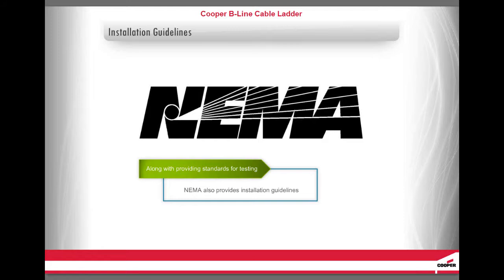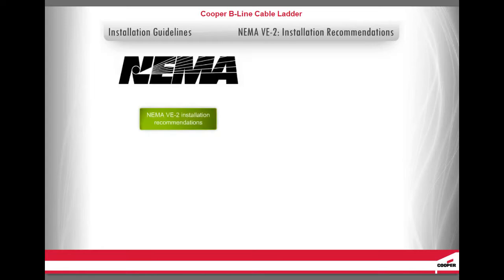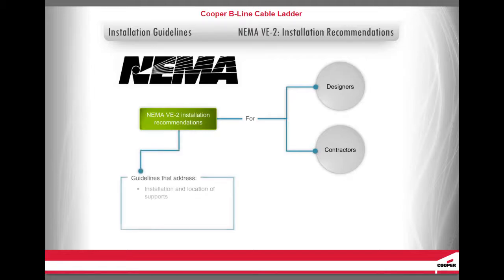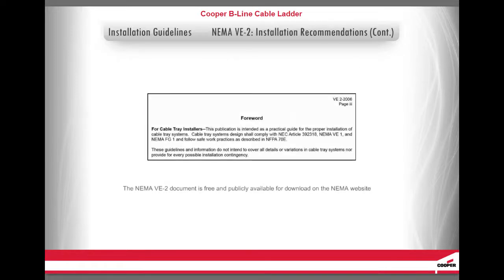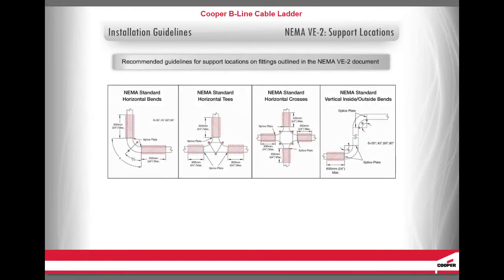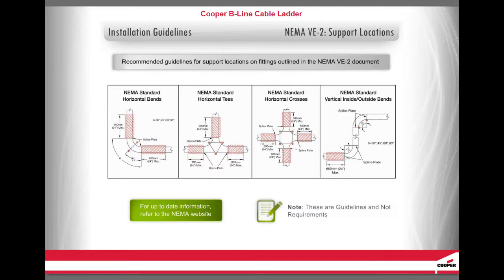Along with providing standards for testing, NEMA also provides installation guidelines. The NEMA VE2 installation recommendations are for designers and contractors. They are guidelines that address installation and location of supports, field modifications, grounding and bonding, as well as handling and storage. The NEMA VE2 document is free and publicly available for download on the NEMA website. Here are the recommended guidelines for support locations on fittings outlined in the NEMA VE2 document. For the most up-to-date information, refer to the NEMA website. Note: these are guidelines and not requirements.